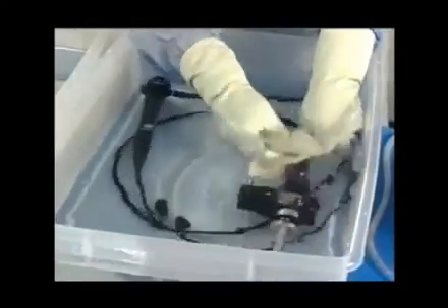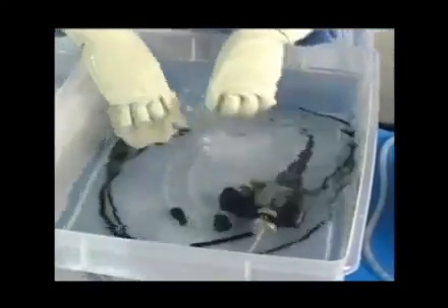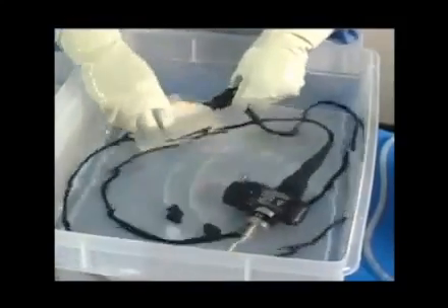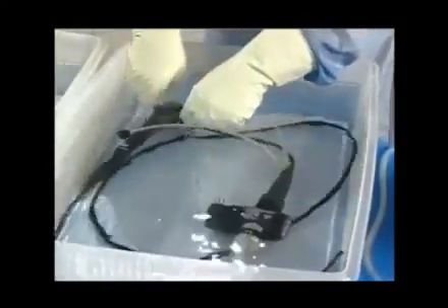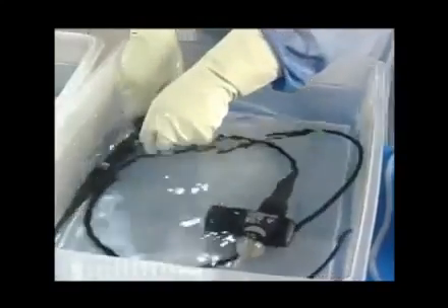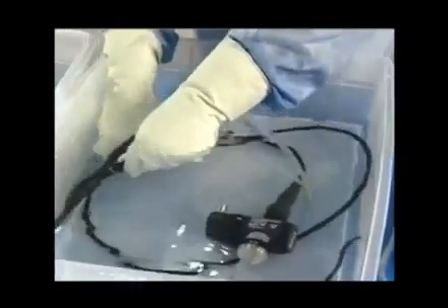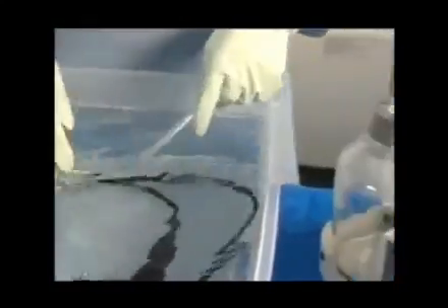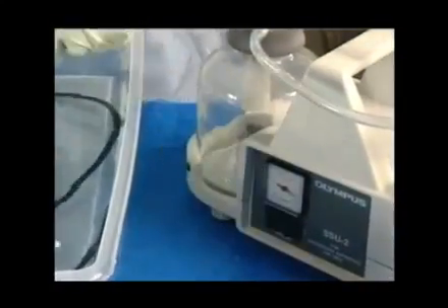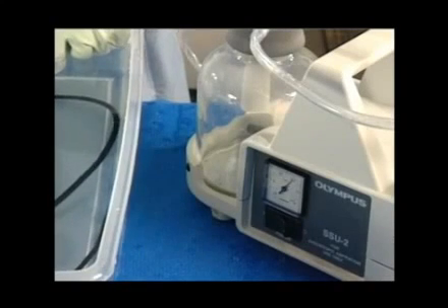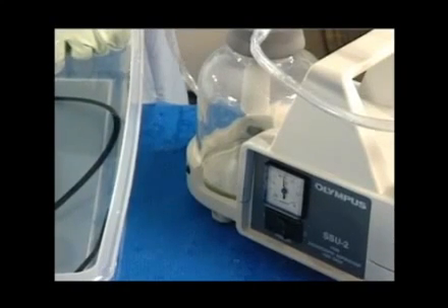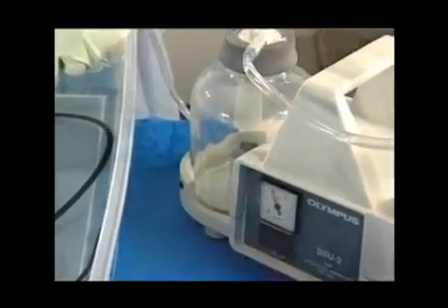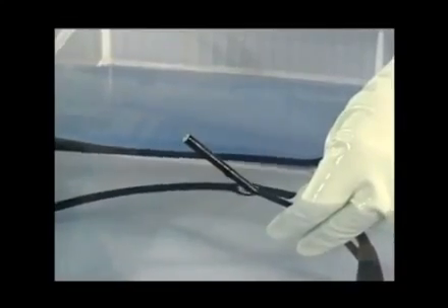Use a clean, lint-free cloth to wipe the outside of the endoscope. Reconnect the suction cleaning adapter and connect it to a source of suction. Aspirate rinse water through the channels for 30 seconds. Remove the bronchoscope tip from the rinse water and aspirate air for 20 seconds.